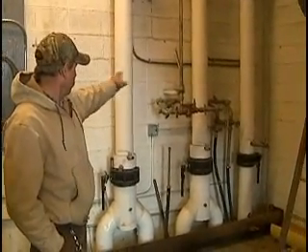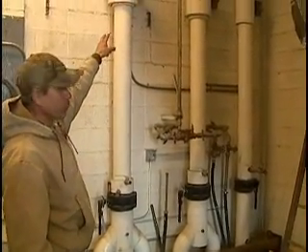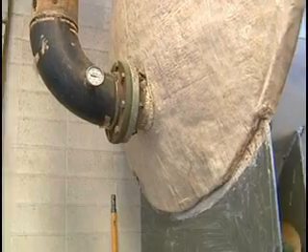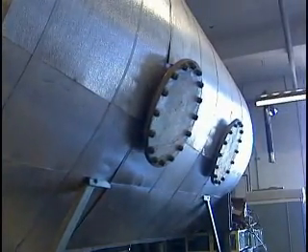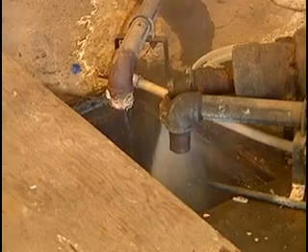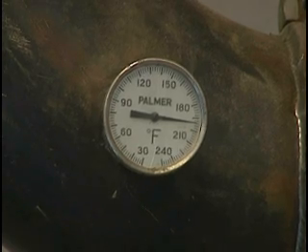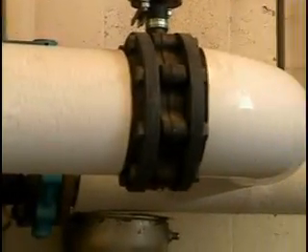After our production wells, wells two, five, and six come into this building through a flow meter — a vortex flow meter — that measures how many gallons a minute we're pumping out of each well into this tank. This tank basically holds the hot water to be ready for campus as the heating demands are called for. The temperature at this time coming in from the wells is at 193 degrees. It's about a 4,000-gallon storage tank. It's the gravity feed for the campus because it's all downhill, and it provides the head for our distribution system so we don't have to pump after we get it out of the wells.